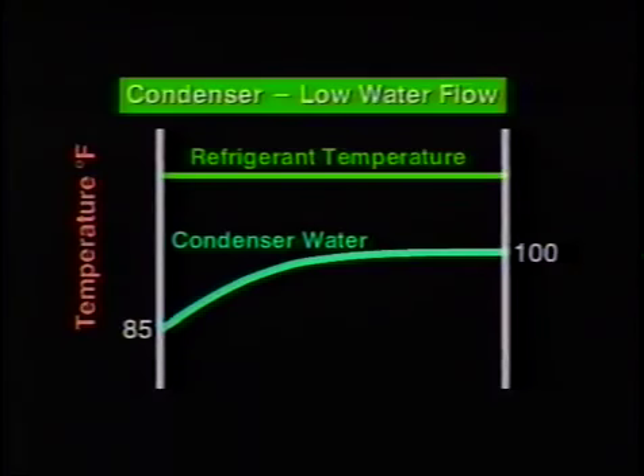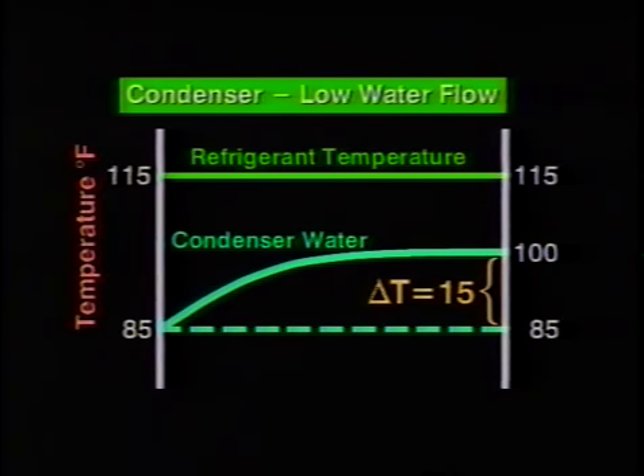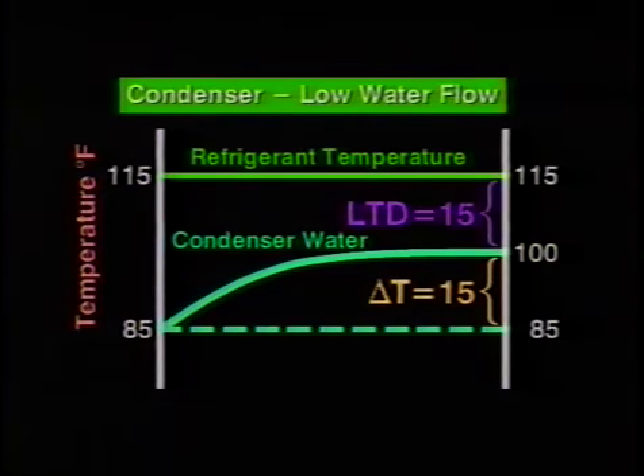Low water flow would cause the delta T across the condenser to rise, and since the total heat transfer is less, the head pressure will also rise. In this example, we see a saturated condensing temperature of 115 degrees Fahrenheit, a 15-degree delta T across the condenser, and an LTD of 15 degrees.